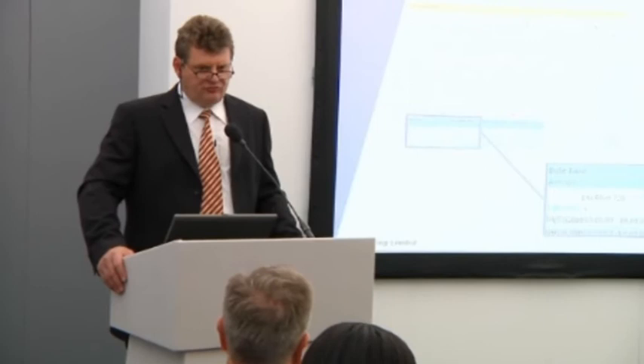For these guys to achieve less than 1.2 is a real world-class performance. Google claimed to have the most efficient data centres in the world at around 1.2. You see some very bespoke designs now being put forward, but they are really based on very custom-engineered solutions for fixed-size data centres. To take a legacy data centre, retrofit a simple piece of equipment, and achieve this world-class performance is a position they're rightly very proud of — and, of course, financially makes a very big difference.